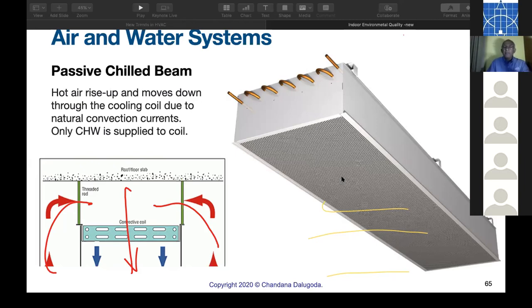Again, like the chilled ceiling here, the surface temperature is above the dew point temperature of air. If you need to tackle high humidity, you'll have to send dehumidified air to this place as a secondary mode. Otherwise, we can't do that.